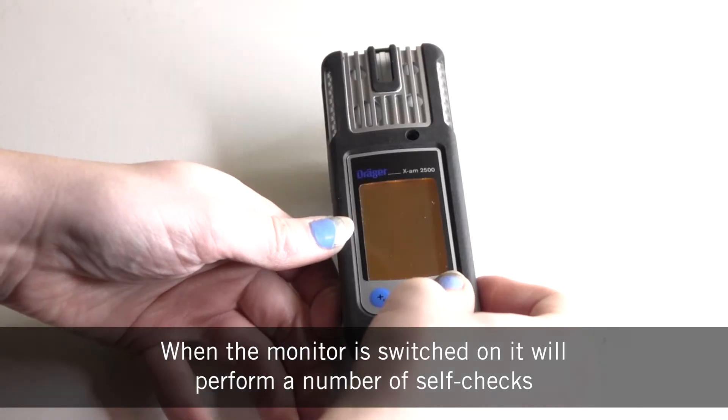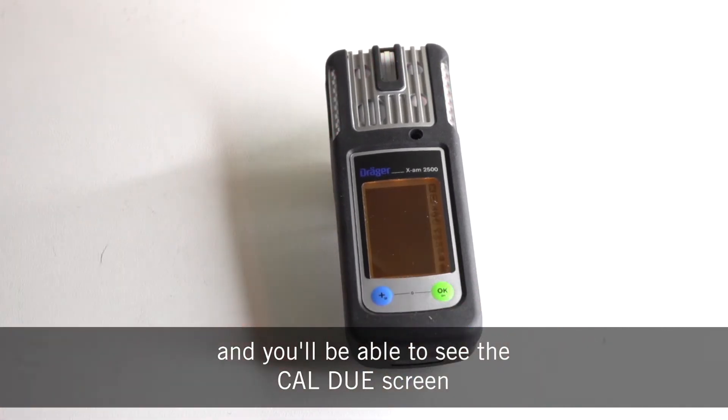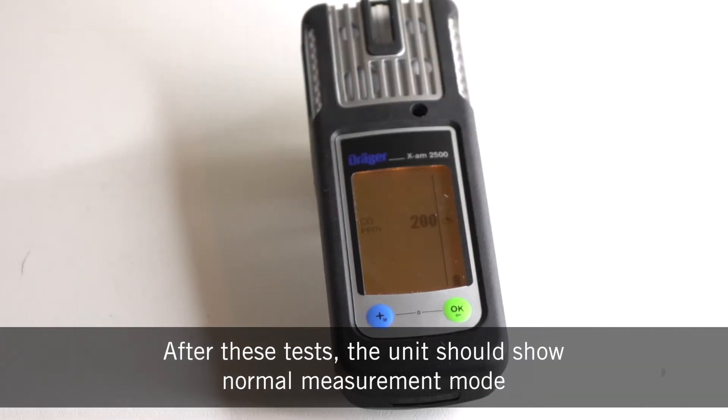When the monitor is switched on it will perform a number of self-checks and you'll be able to see the CAL DUE screen. After these tests the unit should show normal measurement mode.